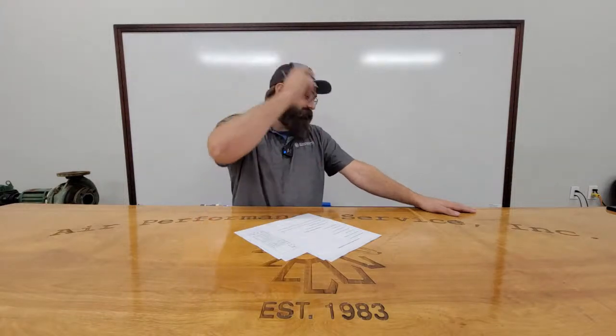The vane dampers, what are they? Just like when you have a damper on a motor, inlet guide vane. So you can do inlet guide vane, which is a constant speed motor. It's just on or off. And then you limit the amount of airflow that can come into the fan by a vane.